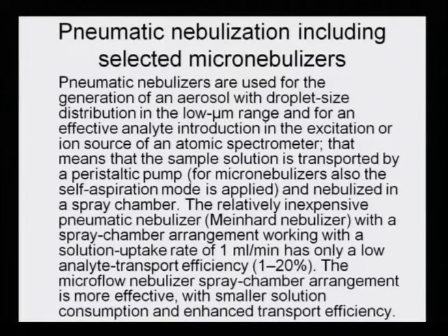That means the sample solution is transported by a peristaltic pump, for a micro nebulizer also. The self-aspiration mode is applied, so it kind of sucks on its own. There is self-aspiration and there is this peristaltic pump which pushes the solution toward the nebulizer. Then it is nebulized in the spray chamber, so it does not get wasted; there is a proper glass spray chamber within which the aerosol forms.